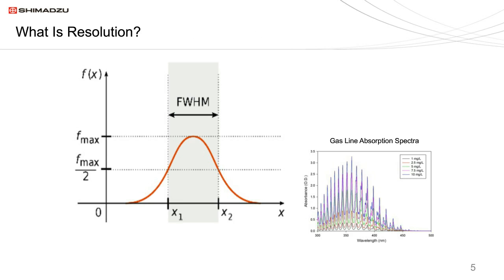Let's take a quick look at spectral resolution and how it's defined for a spectrophotometer. On the left, you see a typical Gaussian peak, and resolution is defined as the full width at half maximum, or the half bandwidth. This is determined by measuring to the top of the peak, labeled F max, and going halfway down. That width across the peak at half the peak height is considered the half bandwidth. On the right is a gas phase spectra which has a number of sharp peaks, showing how resolution can be important if you have narrow bands you need to resolve.